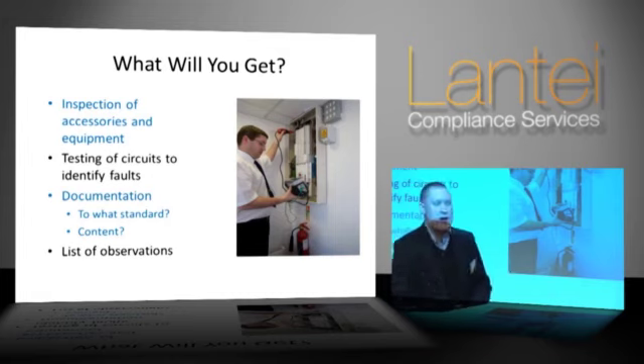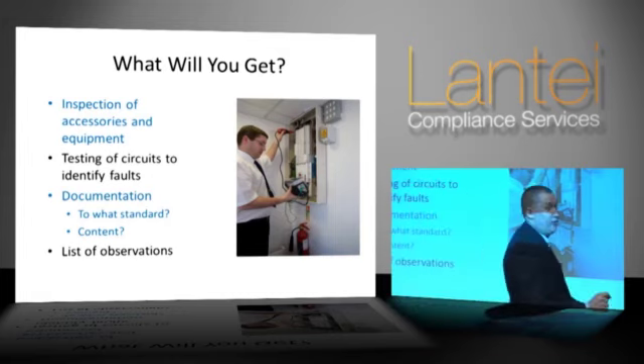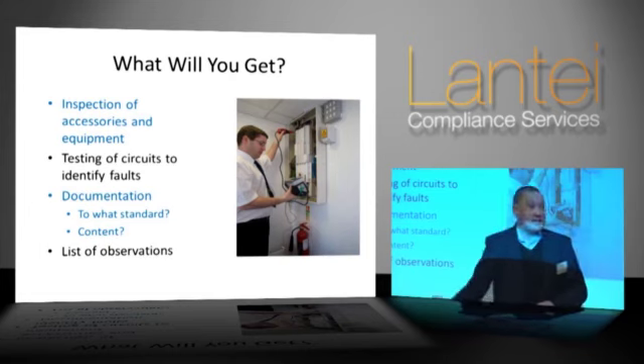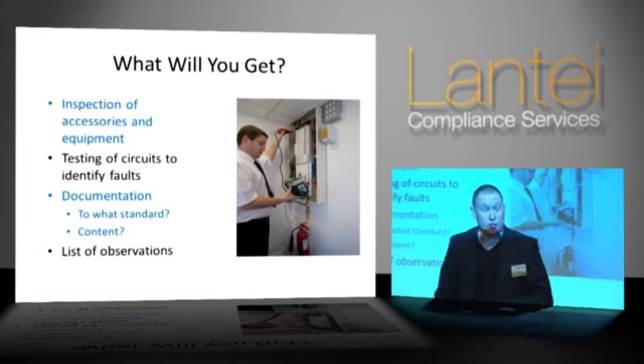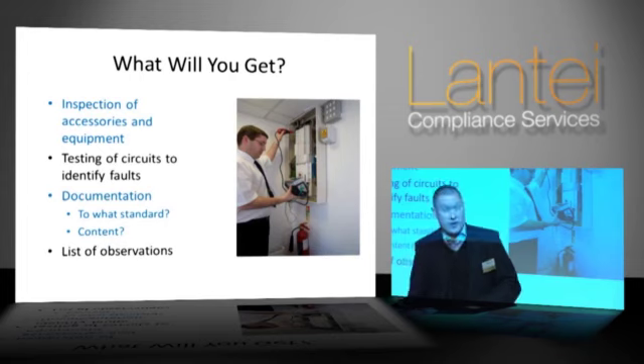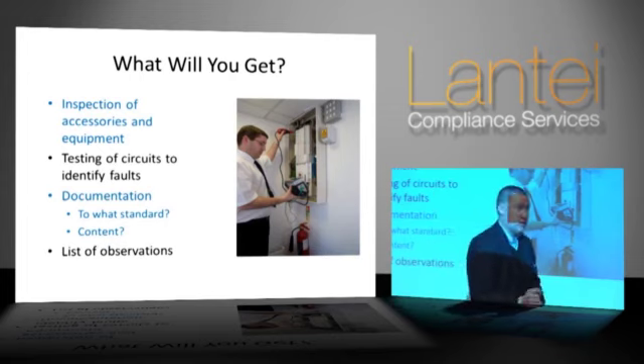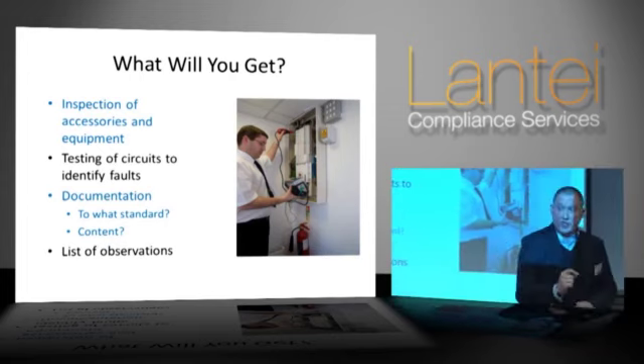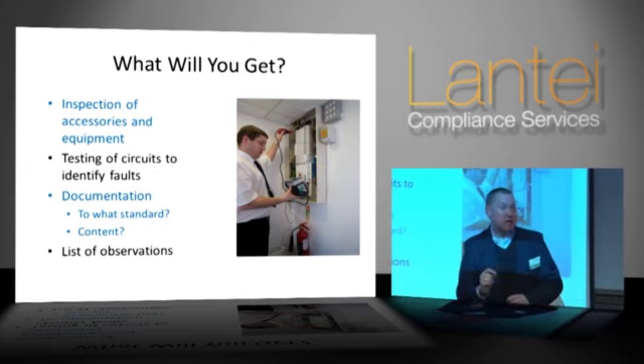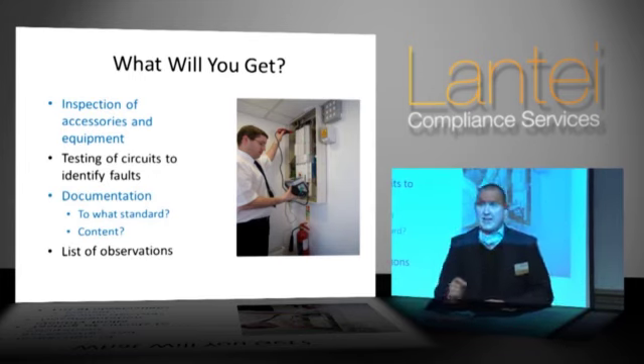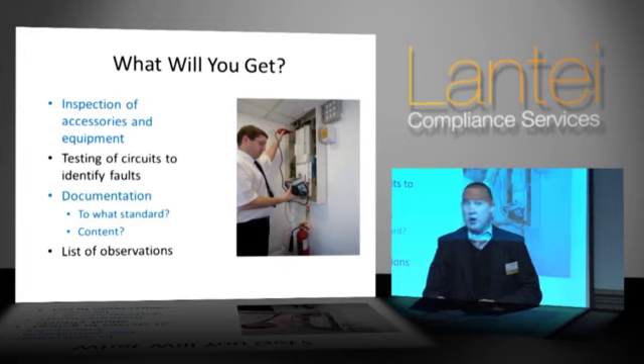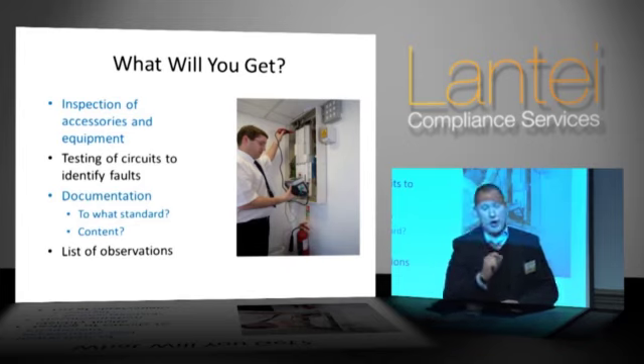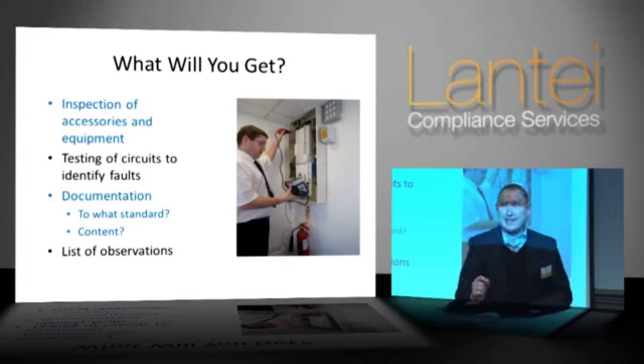The only reference to 10% anywhere in IET documentation is in Guidance Note 3, and it refers specifically to the inspection of accessories and equipment. It says that, as a bare minimum, you should inspect a 10% sample of equipment and accessories on every circuit you are inspecting and testing.